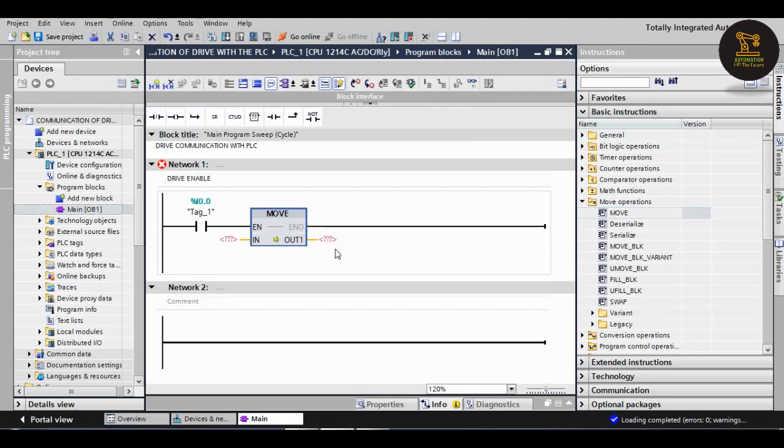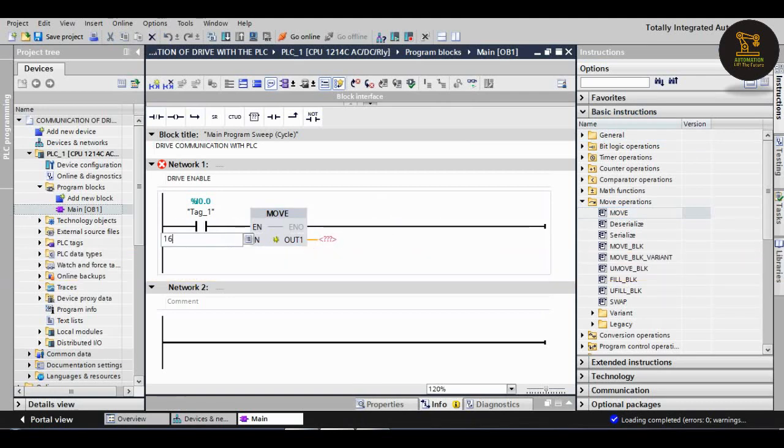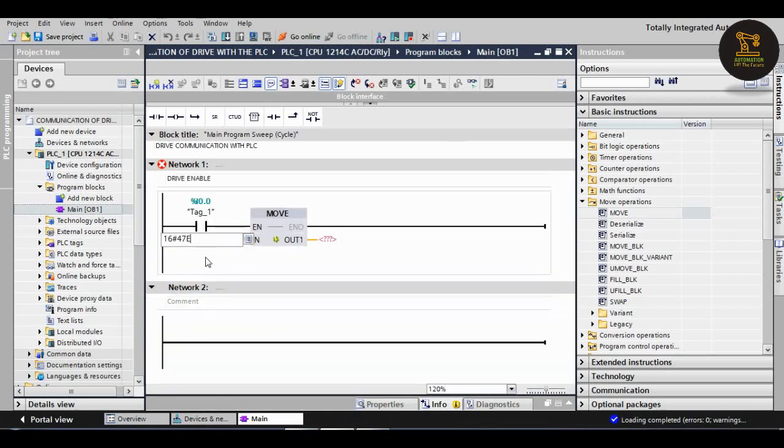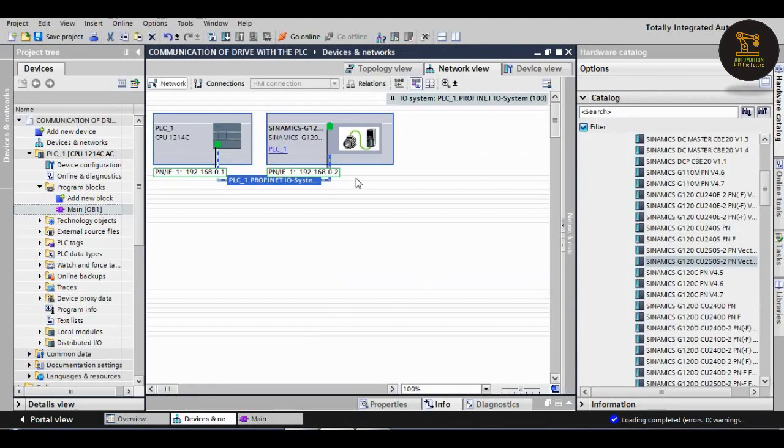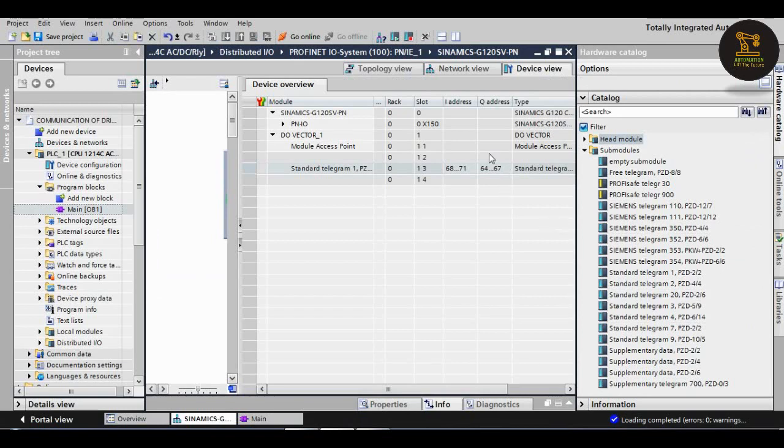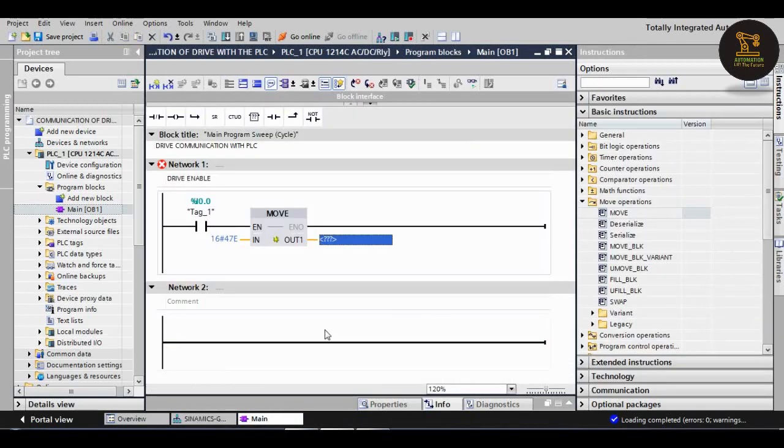We should give here the input 16#47E. We should give this for drive enable. And the output, we should give here, we should check the output. Double click on the drive, output address is 64, means we should give here QW64 as output.